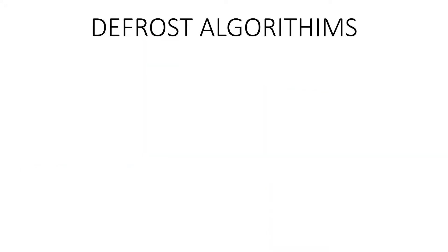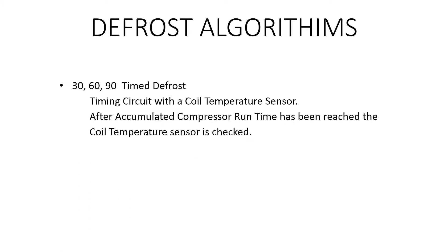There are basically two defrost algorithms used on most modern heat pumps. The first is a timed defrost: a timing circuit with a coil temperature sensor checks the coil temperature after the accumulated compressor run time has been reached. If the coil needs to be defrosted, it will go into defrost. If defrost is not needed, it will reset the timer and go around for another timed circuit.